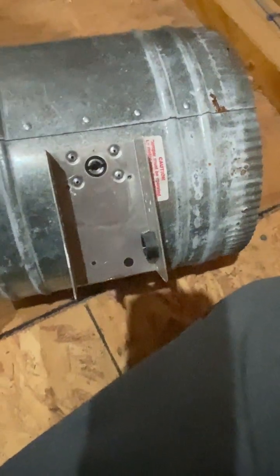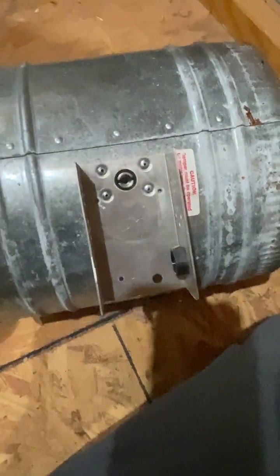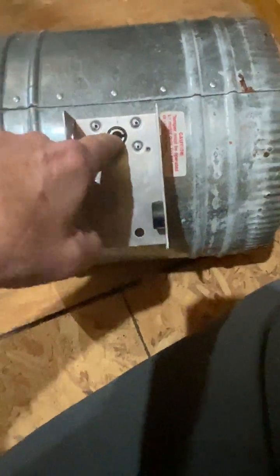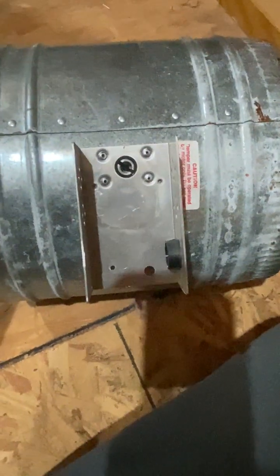This is what a zone control valve looks like on the inside. You see, it is set to be normally open. This one has a spring. This is the old style. It has a spring on the inside, which brings it back to the open condition. And over here is where the valve control works, and it gets mounted in this box. It's a little electric motor, 24 volts AC. And as I move the inside, you can see right here where the motor has a key to it, and this would be normally closed. So all the motor has to do is go against the spring tension that's in the valve.